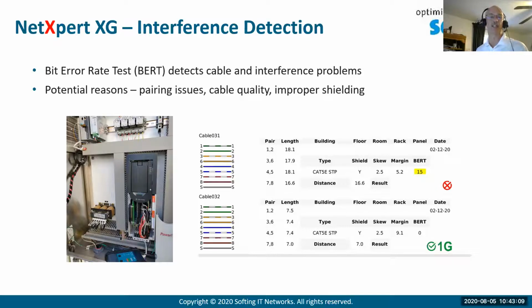All the diagnostics showed the network was fine, the cable was fine. The type of cable tester they used said the wiring's good, the shield's there. I disconnected both connectors, from the switch and from the PowerFlex drive, hooked up the XG, and ran the test that Tom just showed you. Lo and behold, we had bit error rate failures, meaning there were actual bit errors at 1 gigabit per second on what was just a 20-foot cable.